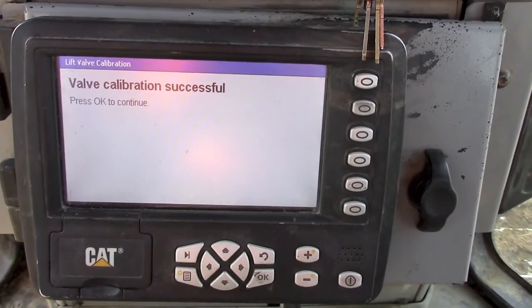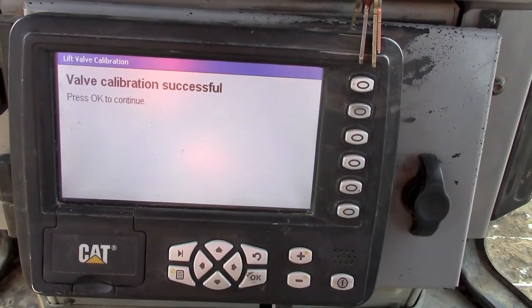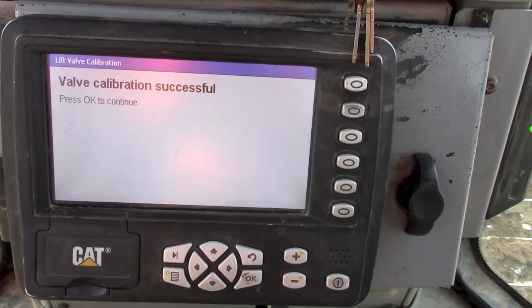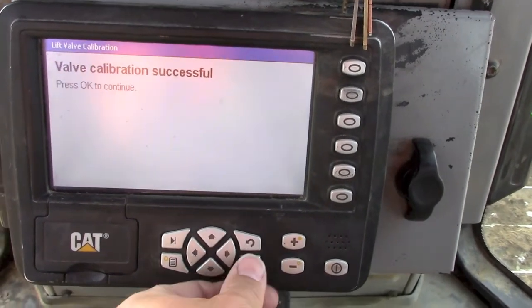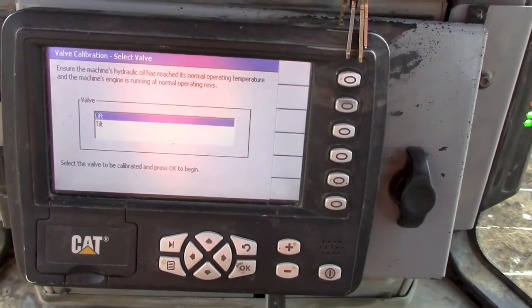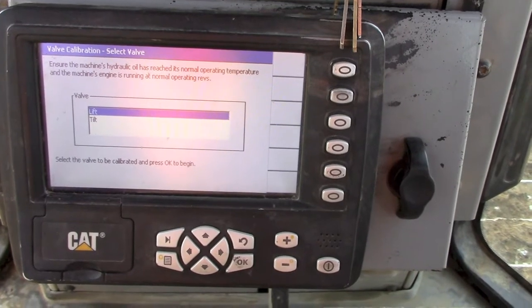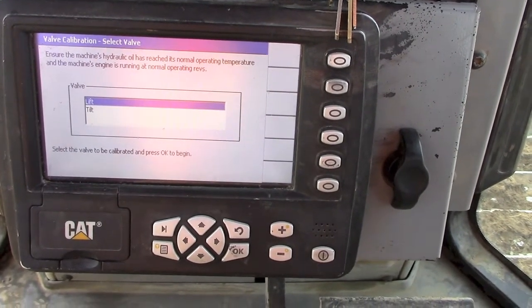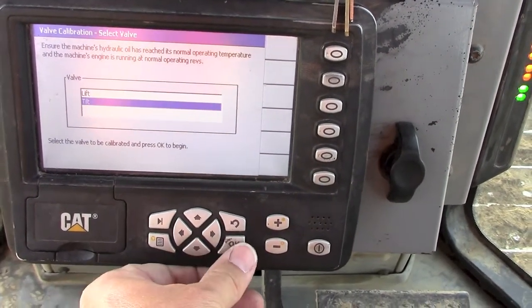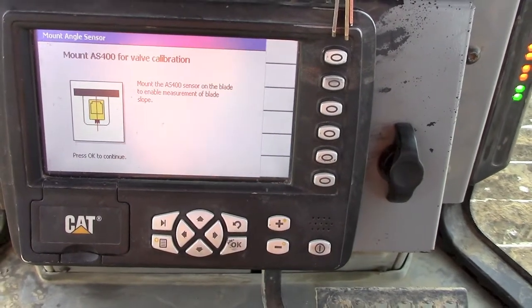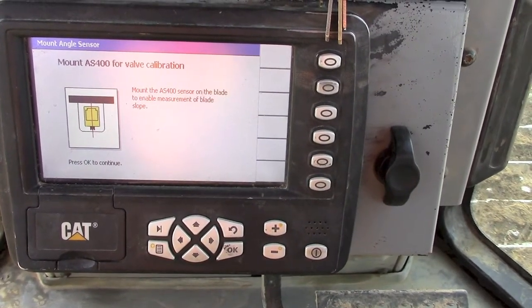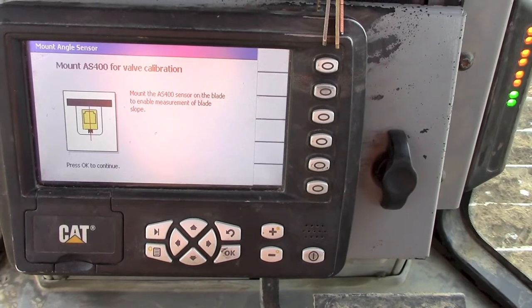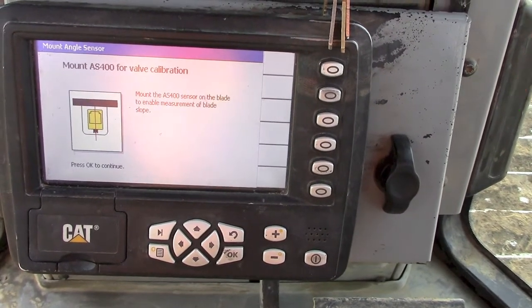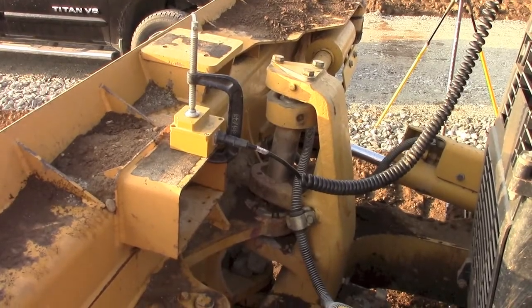About 5 minutes has gone by. We can now see that our valve calibration was successful, so we would press OK to continue. Okay, at this point that was only the lift. We also need to do the tilt. So if we go down to tilt and press OK, it lets us know we need to rotate our AS400 so that the connector is facing the rear. I now have the sensor with the connector facing the rear.